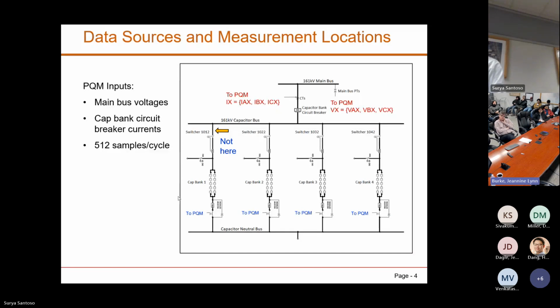You see the issue here - our voltage and current waveforms used for anomaly detection come from this location, not elsewhere. Incidentally, in some substations they have a power quality monitor installed at the load side of the circuit breaker, and they also have 87 relays, the differential protection relays. We don't use any of this data.